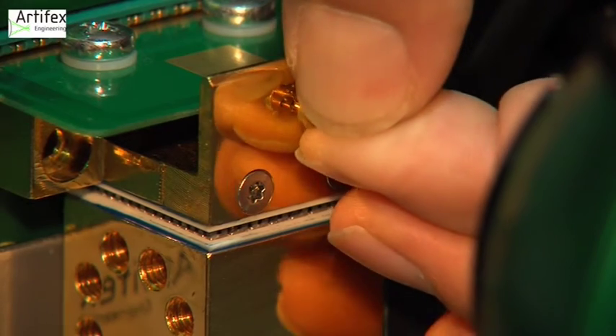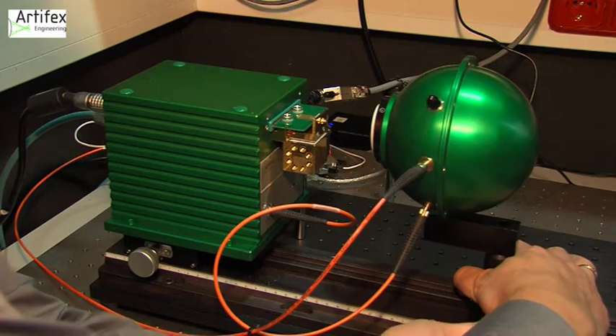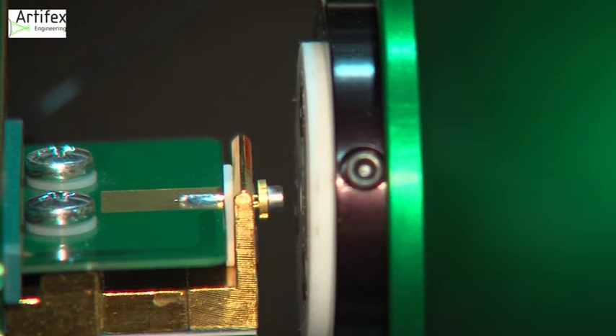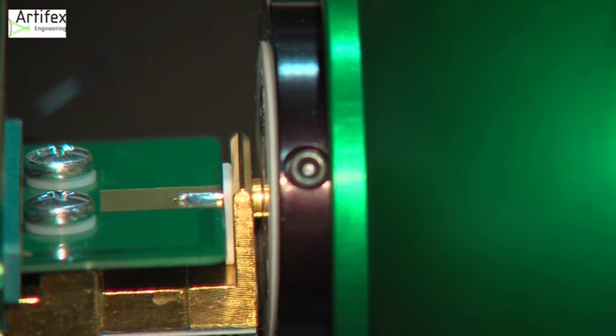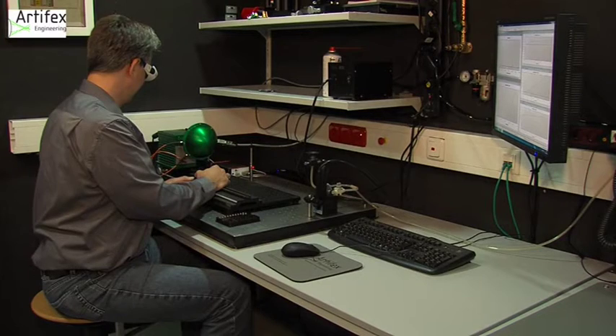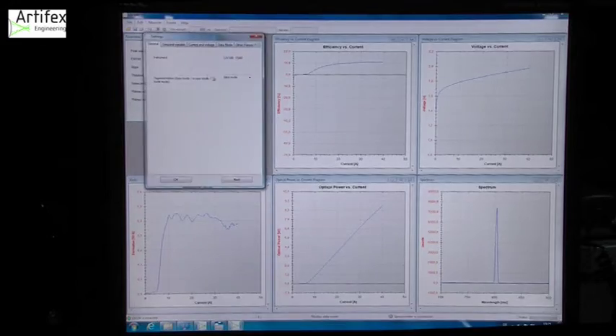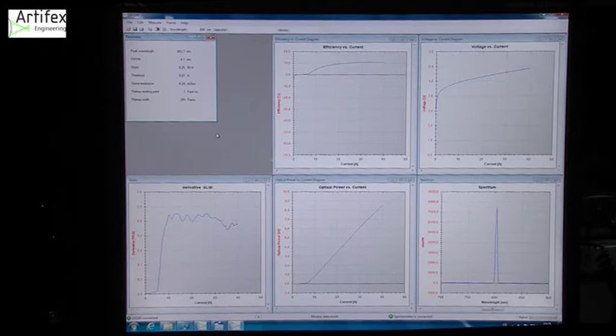TO cans are inserted into the temperature control chuck. Moving the integrating sphere into place forces the device into thermal contact with the chuck. The measurement occurs with a user defined parameter set resulting in a full LIV characterization in less than one second.